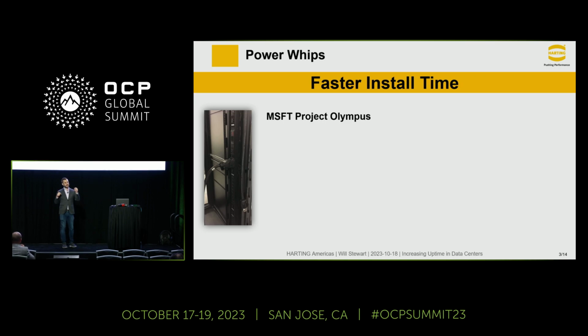By separating the cable from the rack PDU, they were able to create a universal rack PDU that can be used anywhere in the world. And then with that, now you can hold inventory of it. Now your means of production go up, so the costs come down. And the complex side of it with the cable assembly, those could be manufactured by themselves.